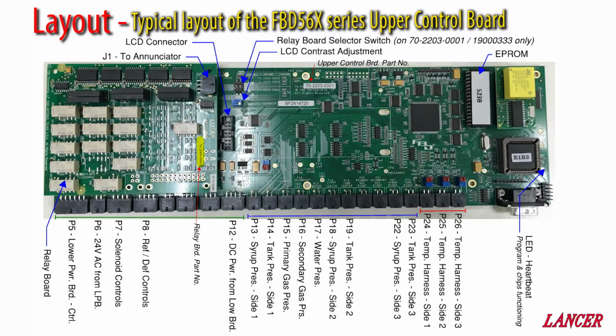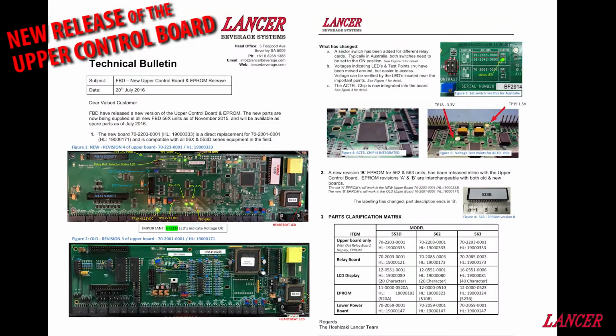This is a summary page to pause and review the connections and components of a typical FBD 560 series upper control board. This is the latest revision board, so please note the relay board selector switch and the relay board part number required to set this position. The technical bulletin shown here is available for review and covers the major changes to the upper control board, such as the test points and LED voltage indicators, EPROM revision, the relay board selector switch. It also includes a parts clarification matrix.